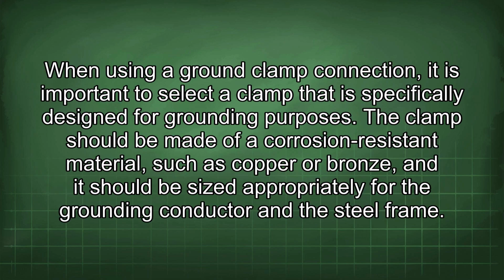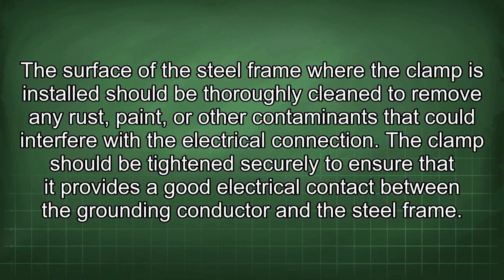When using a ground clamp connection, it is important to select a clamp that is specifically designed for grounding purposes. The clamp should be made of a corrosion-resistant material, such as copper or bronze, and it should be sized appropriately for the grounding conductor and the steel frame. The surface of the steel frame where the clamp is installed should be thoroughly cleaned to remove any rust, paint, or other contaminants that could interfere with the electrical connection.